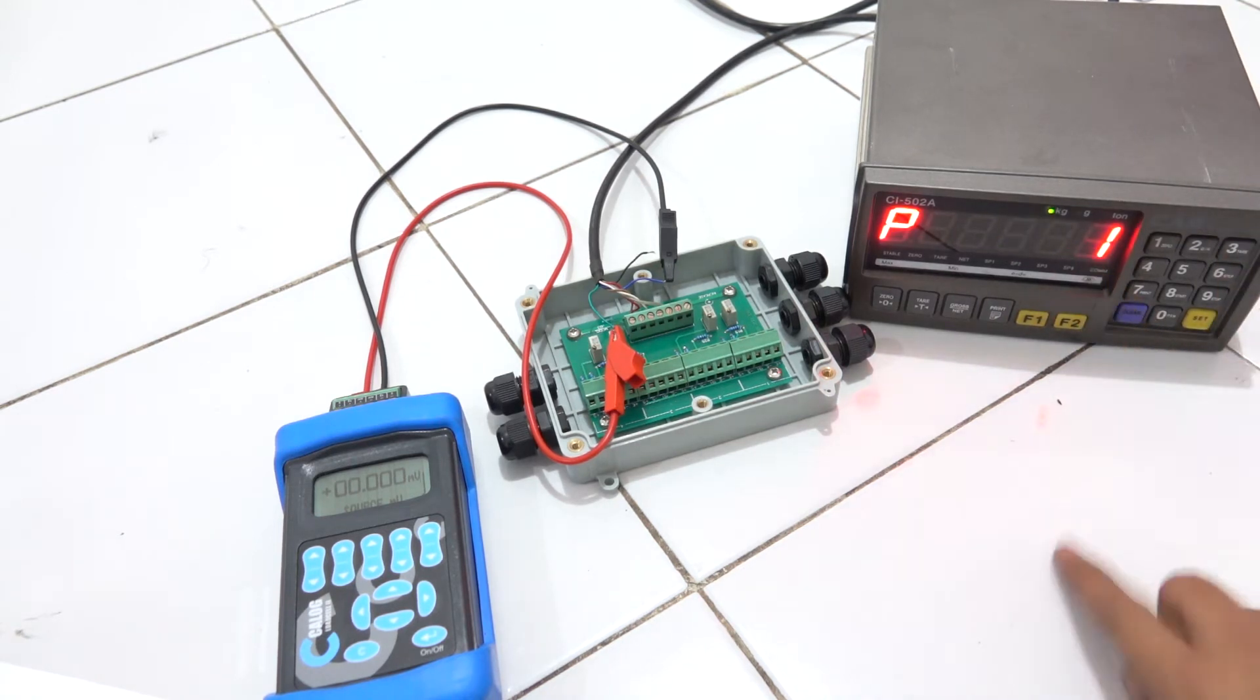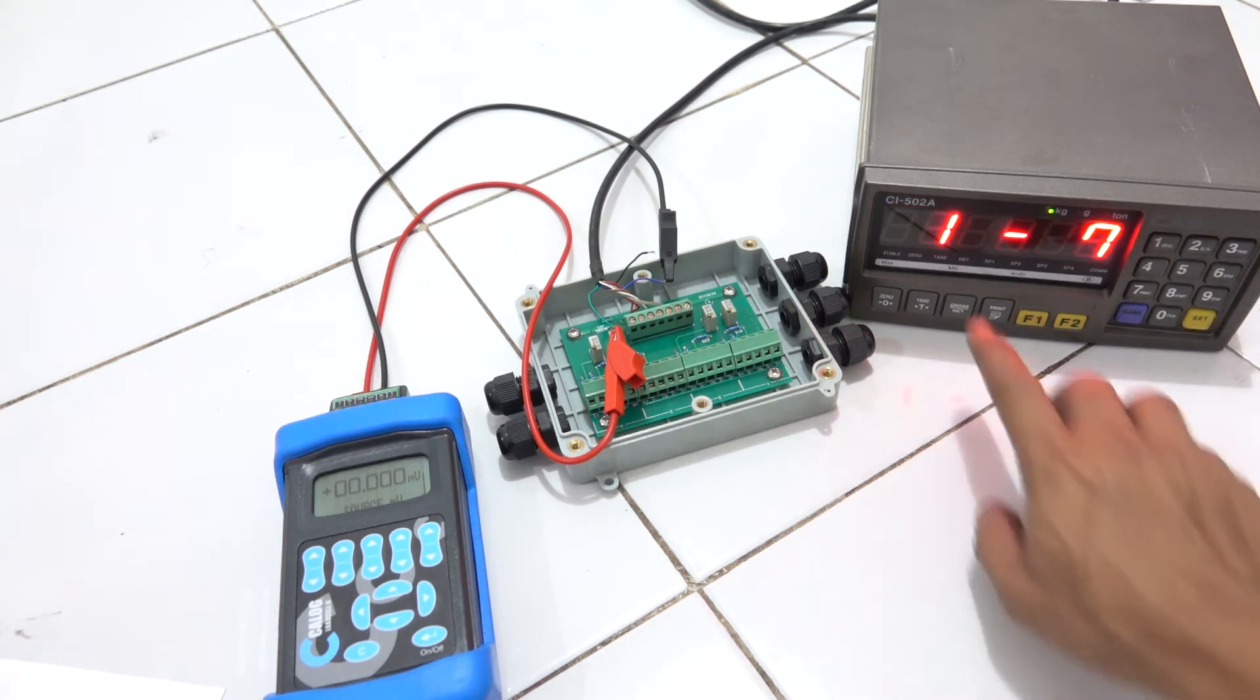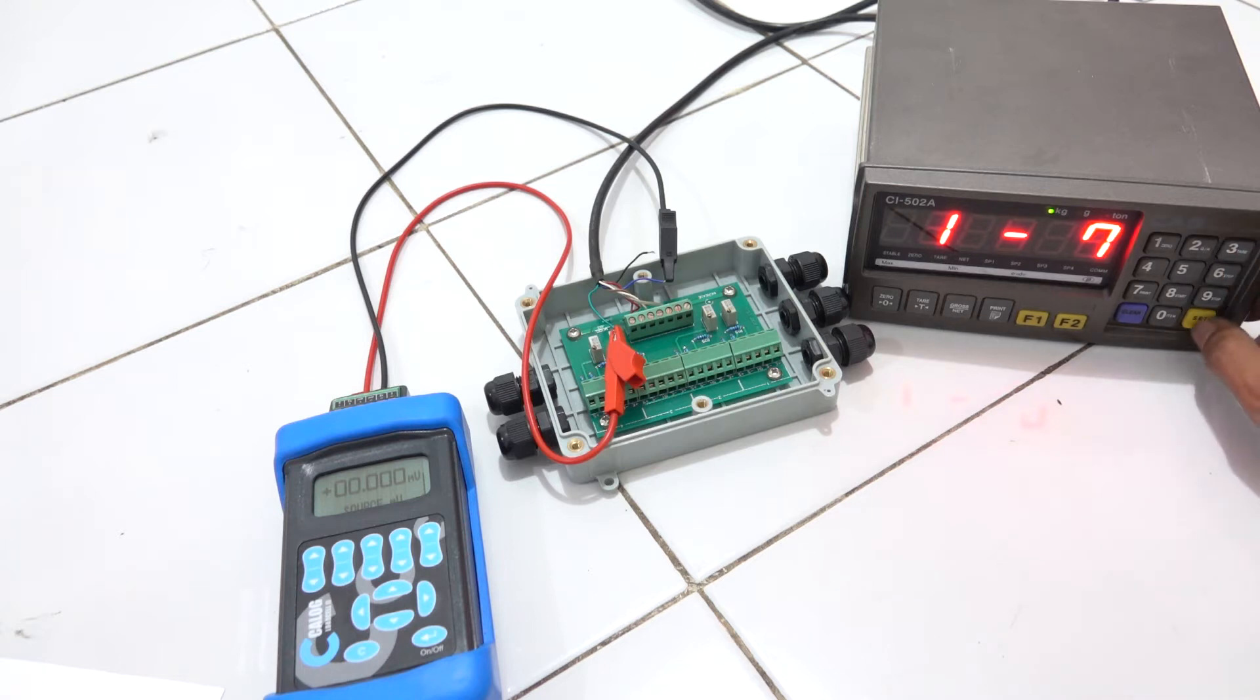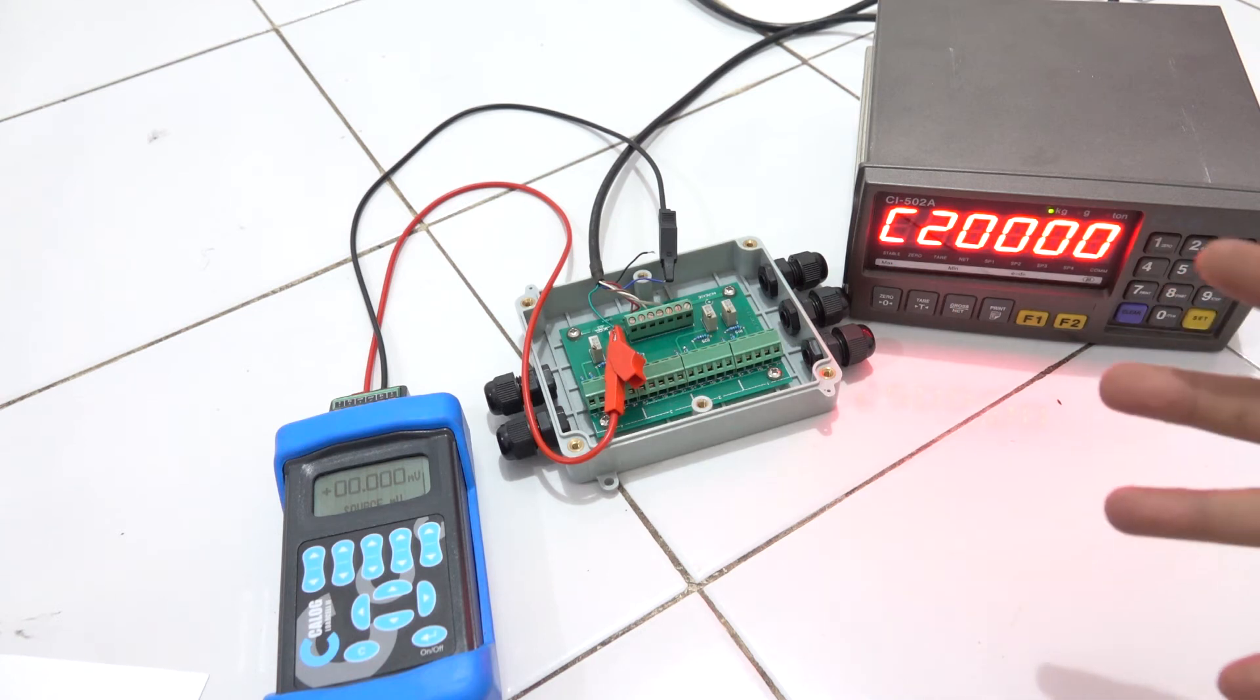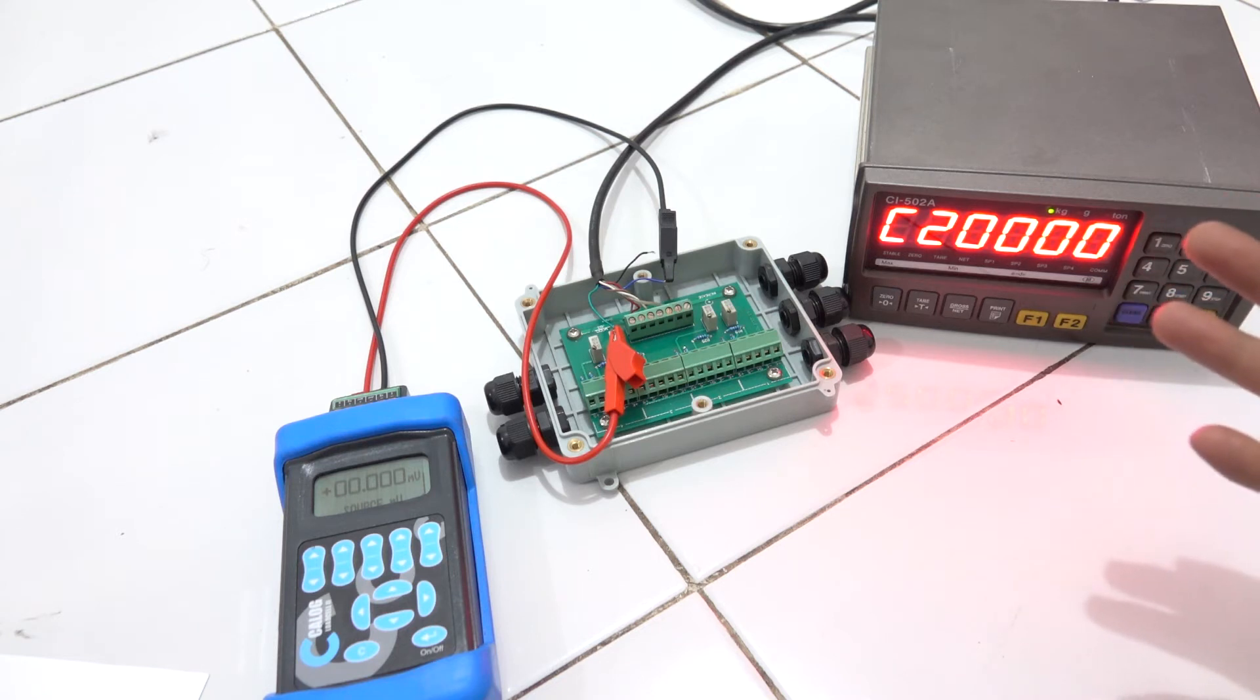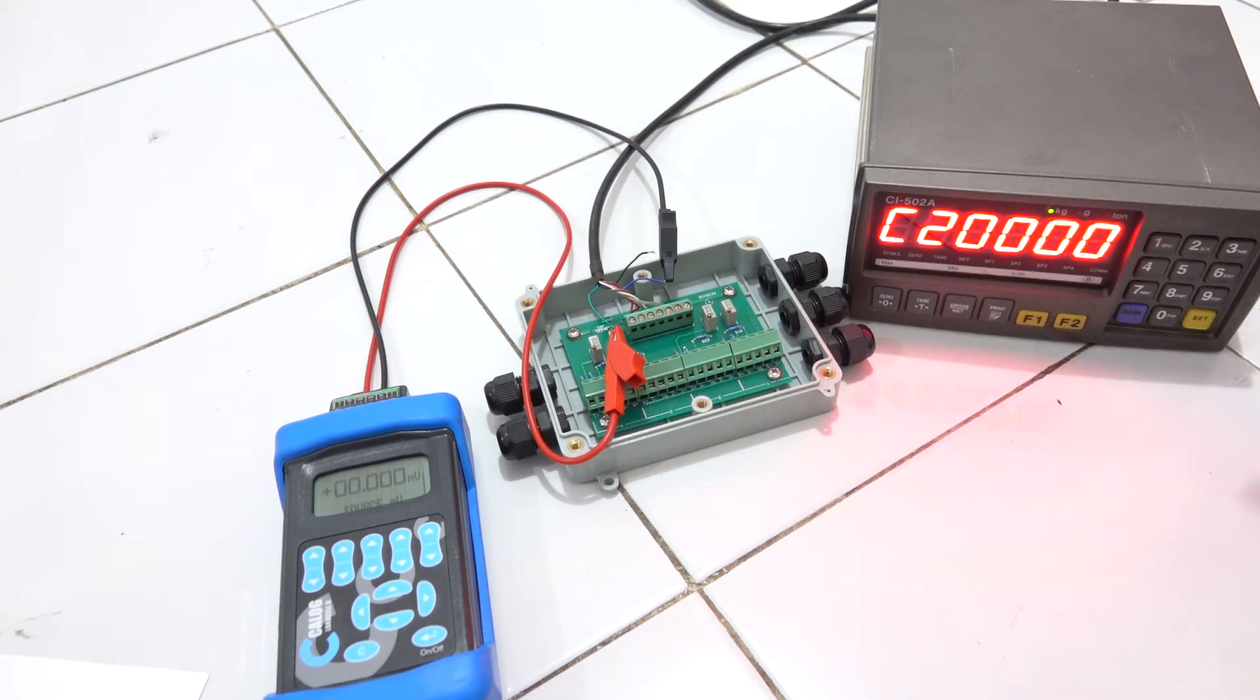C means the capacity of the load cell that you want to calibrate. Let's say the load cell you want to calibrate maybe has a capacity of 20,000 kg, but in this example that I would like to change, maybe only 500 kg.